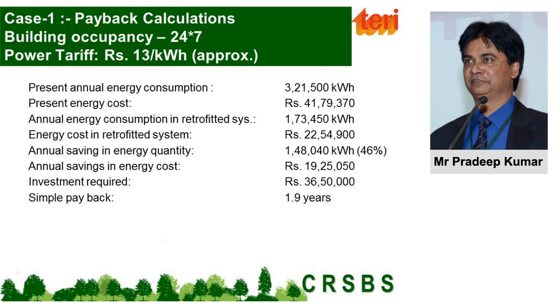Energy consumption, what we found, was somewhere around 3,21,000 units. And cost I will discuss later. Annual energy consumption in the retrofitted case is 1,73,000 units. Cost in the retrofitted case is 22 lakhs. But if you look at the saving of the energy quantity, it is around 46%. I mean, this system is going to save 46%. But look at the saving cost, because the tariff being paid in Gurgaon is 13 rupees per unit, and the payback calculated was 1.9 years.